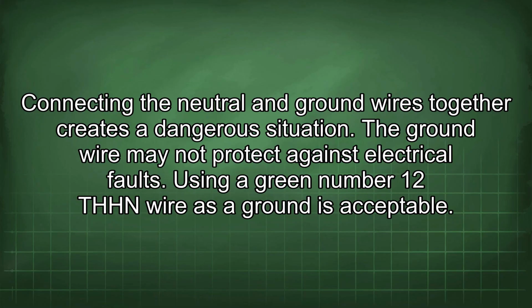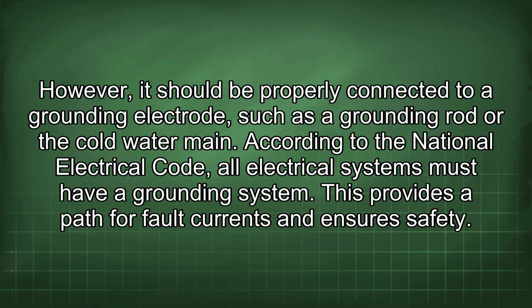Connecting the neutral and ground wires together creates a dangerous situation. The ground wire may not protect against electrical faults. Using a green number 12 THHN wire as a ground is acceptable. However, it should be properly connected to a grounding electrode, such as a grounding rod or the cold water main.